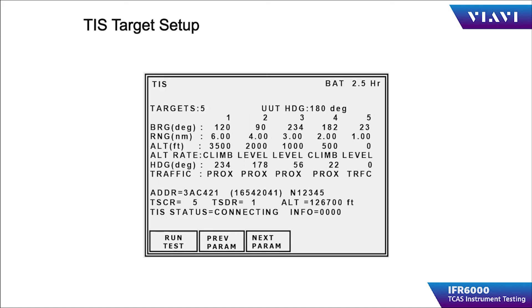The IFR 6000 can simulate a traffic information system broadcast to non-TCAS-equipped aircraft. This information is uplinked via a ground-to-aircraft link provided by the IFR 6000, simulating an uplink from the ATC radar.